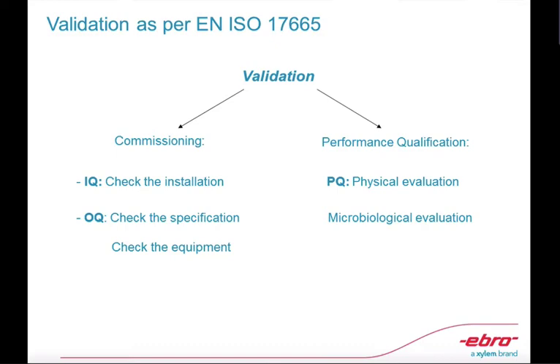Here we go again with IQ, OQ, and PQ, because it is mentioned also by ISO 17665. To your left, the commissioning refers to new equipment, and this also includes refurbished equipment. And to the right is the PQ, which is a cycle that completes the IQ and OQ, but it is also valid for already-used autoclaves in the hospital CSSD units.